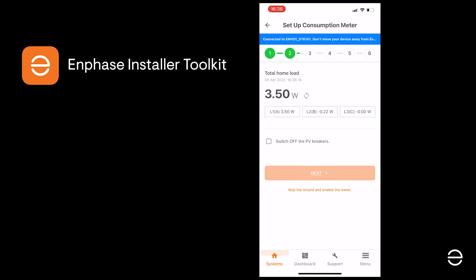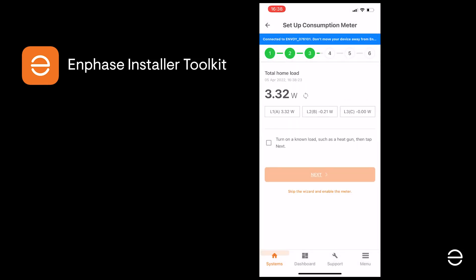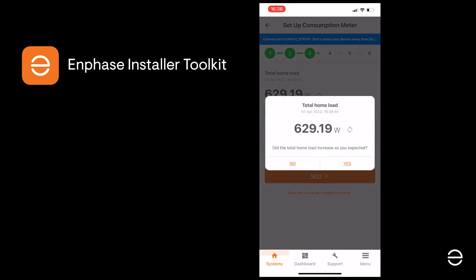Check the box to confirm this is the case and that the PV breakers are off, and click Next. Now we're going to add a significant known load, such as a heat gun for example, to check if the CTs are measuring correctly. When we plug in a known load, as you can see here, the load builds up to what we would expect. If the load does correspond to what you would expect for your installation, click Next. If it doesn't, you need to check the CTs are installed correctly and the arrow is pointing from the PV system or the grid to the breaker box. For details, please watch the video on installing the CTs.